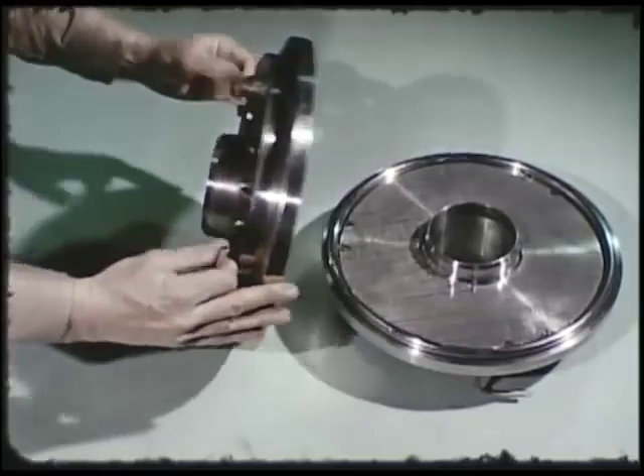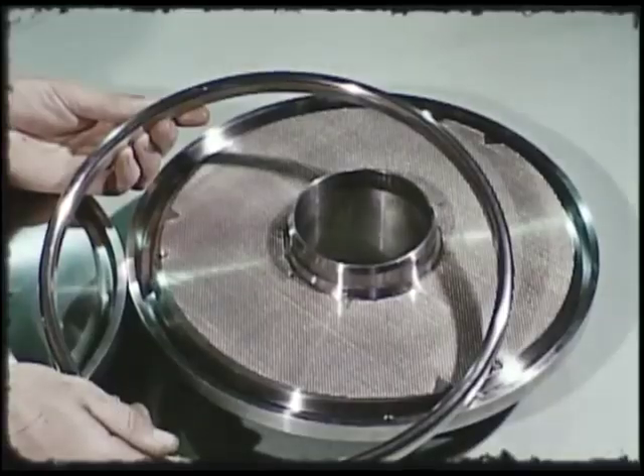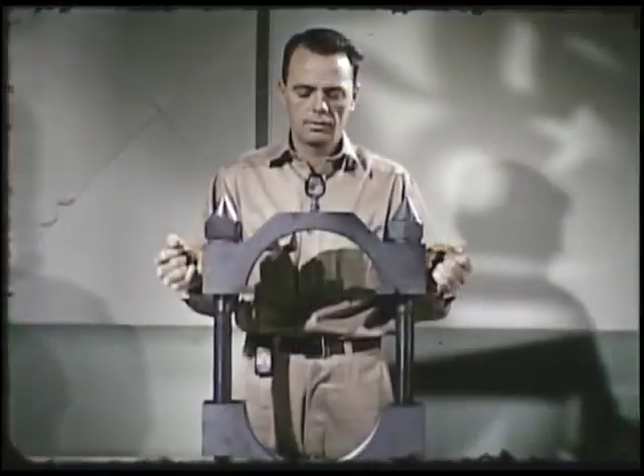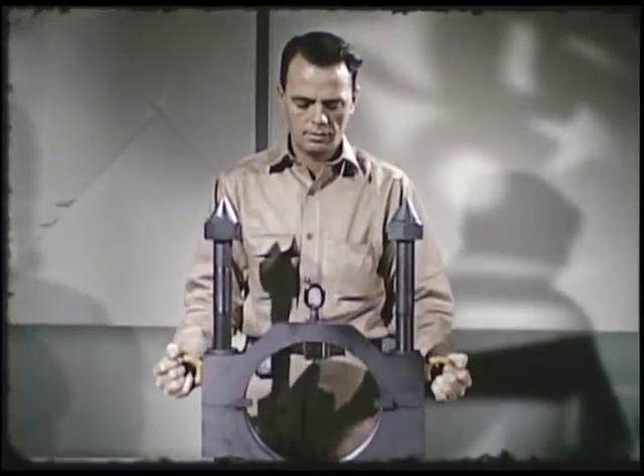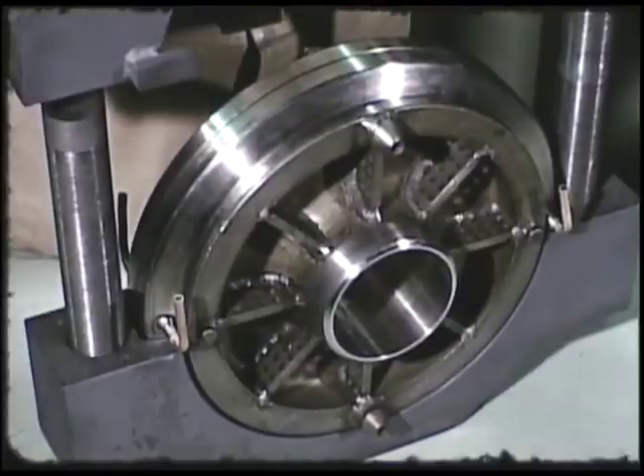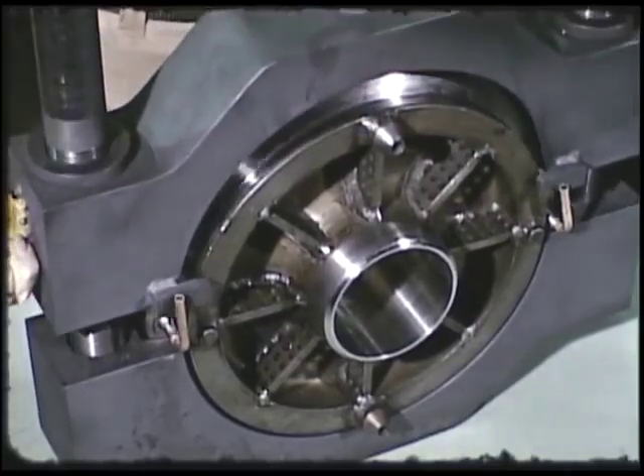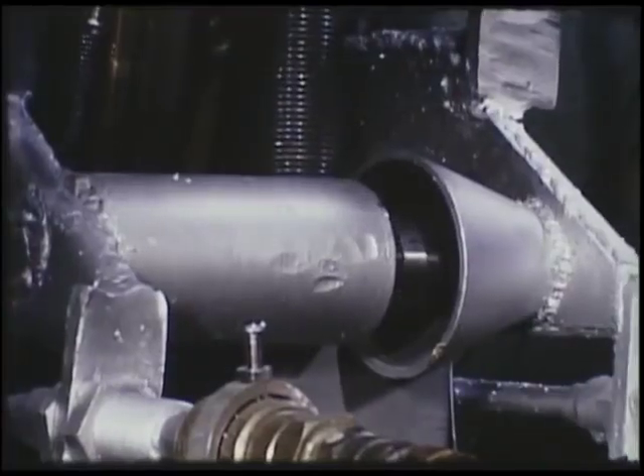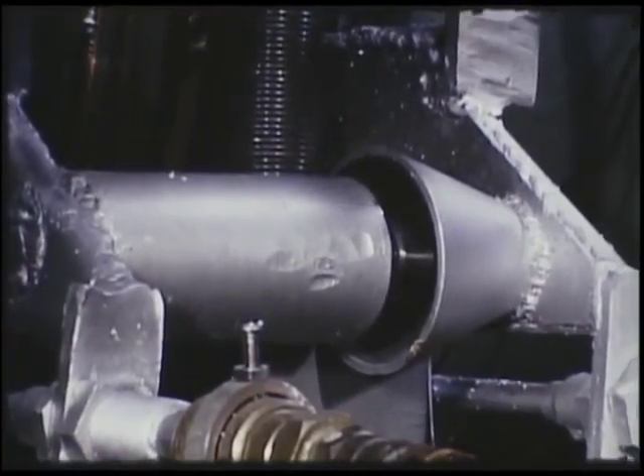This seal is backed up by a conventional metal O-ring, which seals in the fission gases and also serves as a leak monitor. Flanges are held together by two-sectioned wedge clamps fastened by bolts. A 1/16-inch gap exists between the faces. It is in this volume that the salt seal is formed. Pin and funnel guides align the flanges during remote assembly.